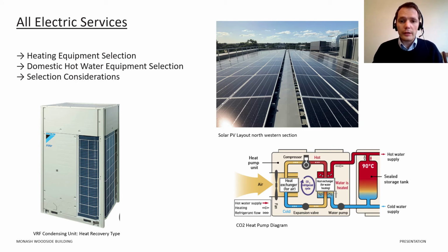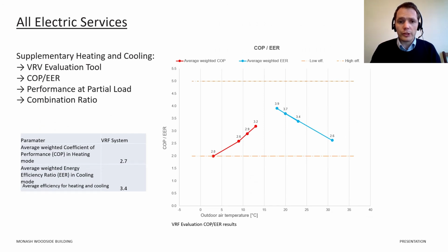If you're all electric, then it makes sense to aim for a reduced PER demand and an increased PER generation. Part load efficiencies are readily available for chillers and heat pumps generating heating hot water. However, this is not the case for variable refrigerant flow systems. We approached the Passive House Institute, who were acting as the certifying body for this building, and with our input they generated a VRF evaluation tool to assist us to determine the electrical demand of the VRF system. The tool takes into consideration the indoor air temperature, which has the boundary conditions of 20 degrees Celsius for heating and 25 degrees Celsius for cooling. The outdoor air temperature boundary conditions is based on Melbourne's weather data file.